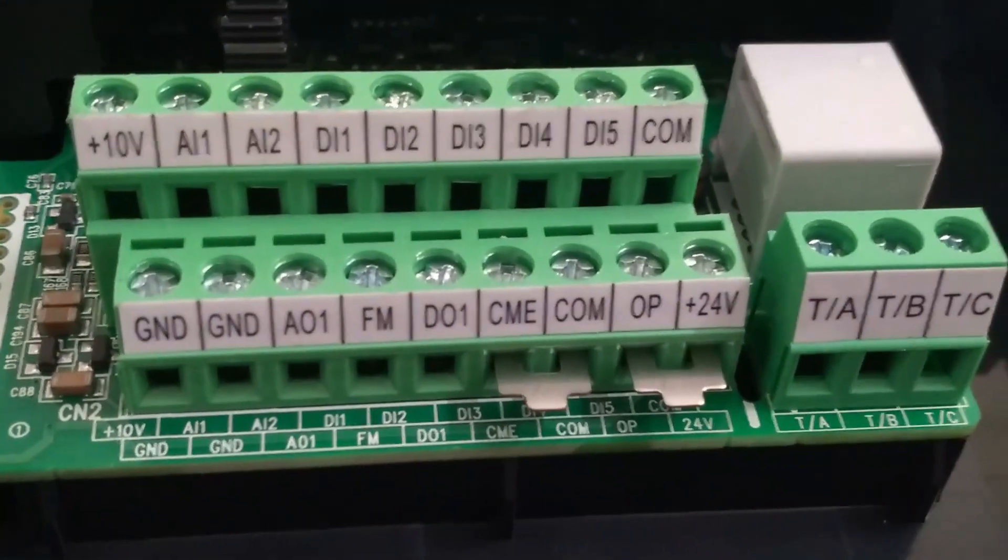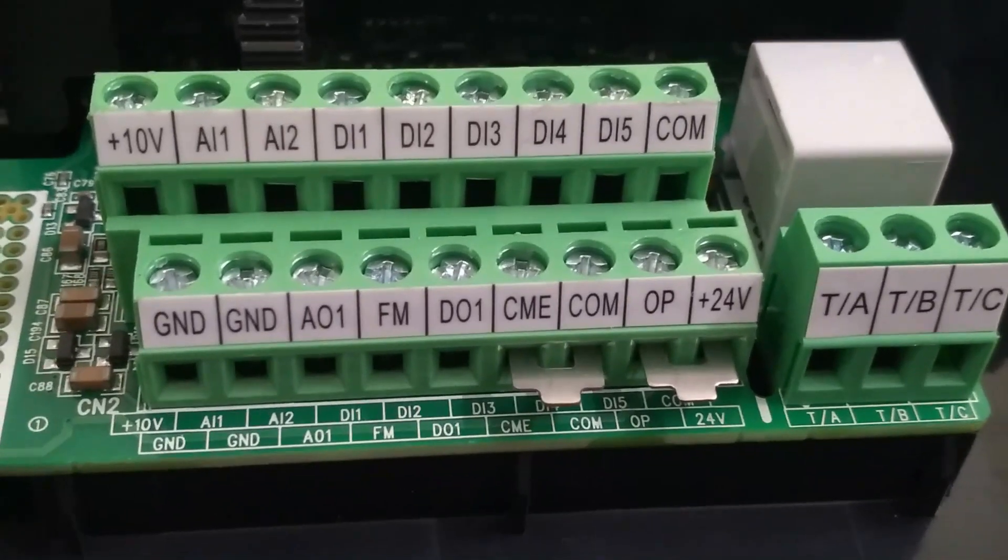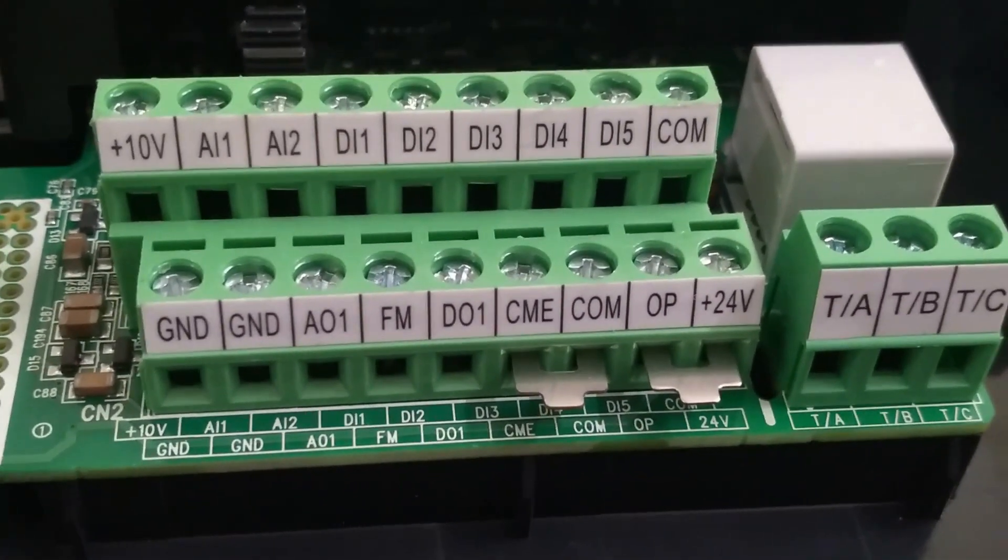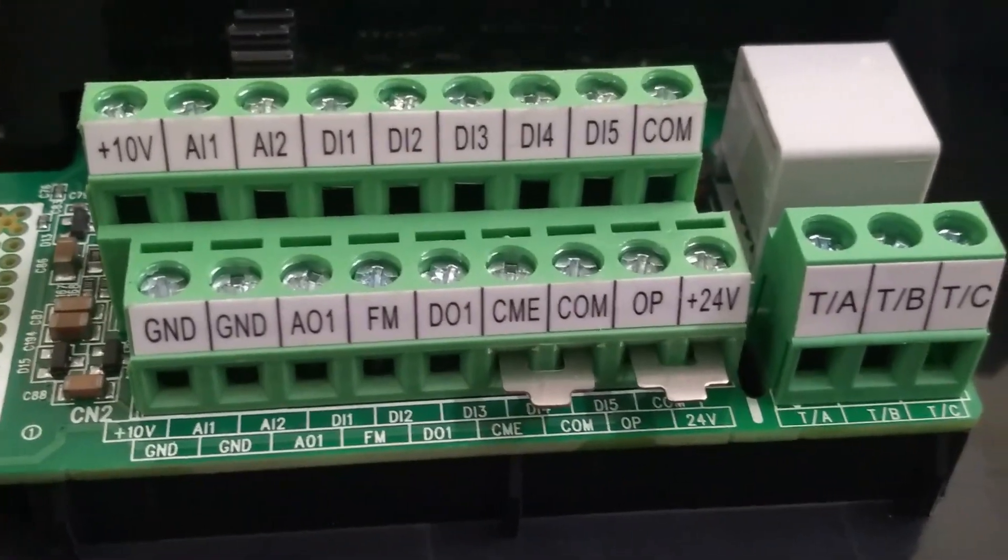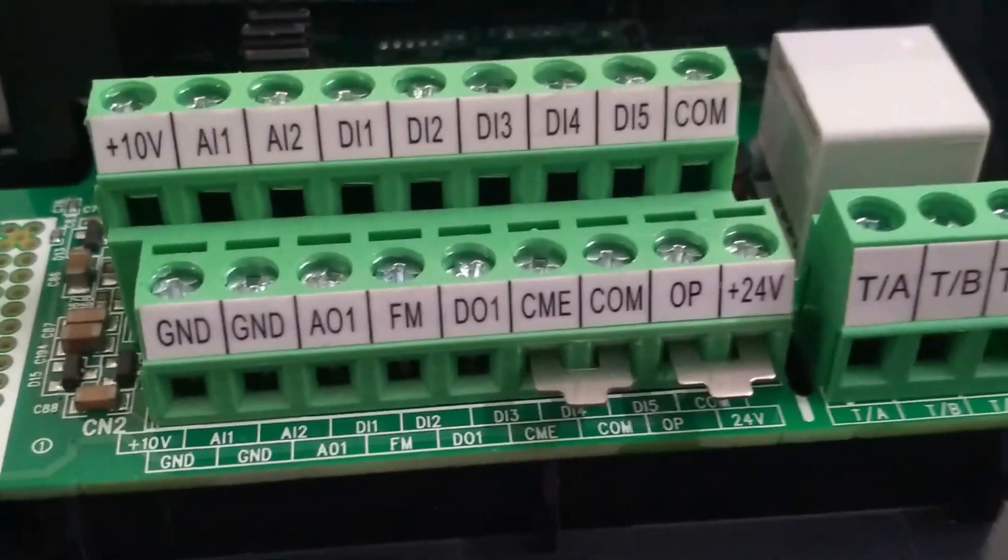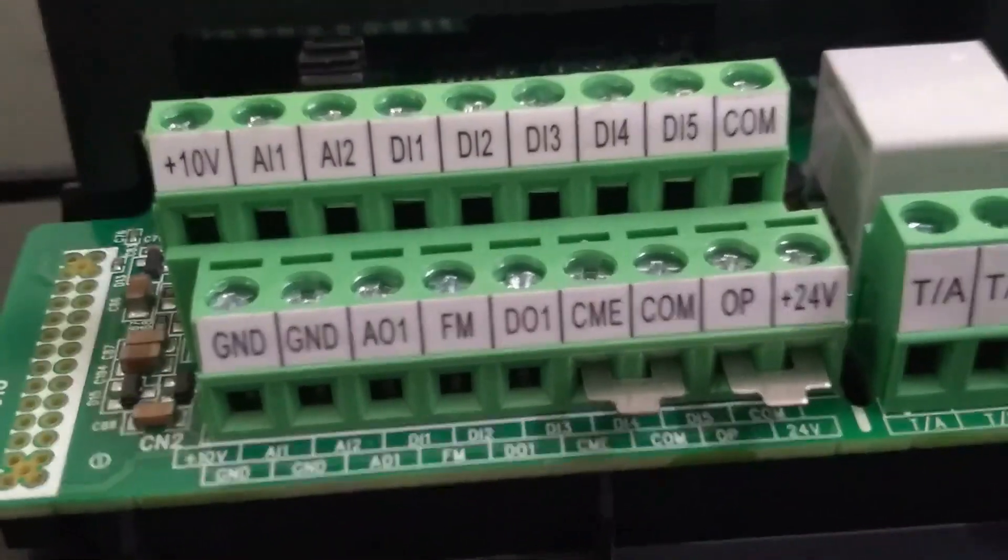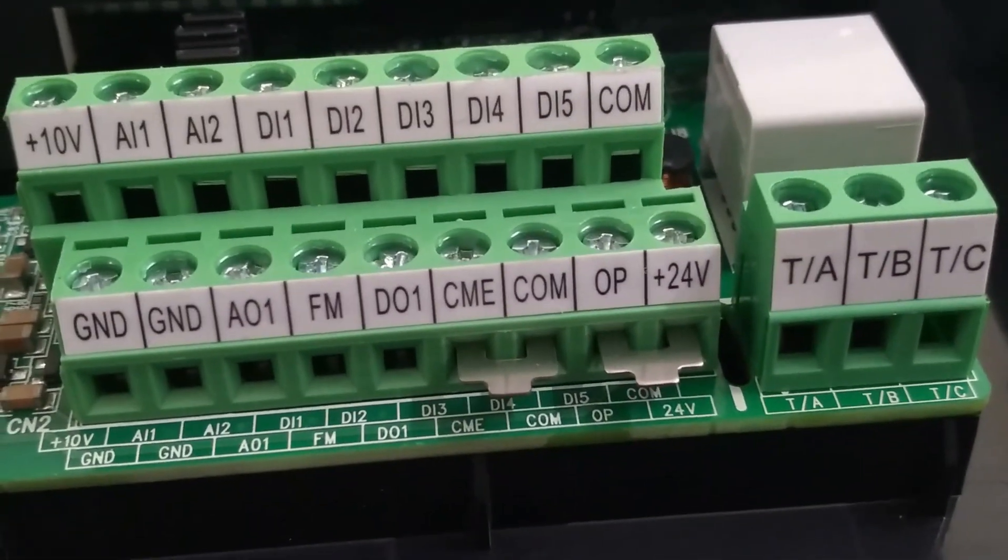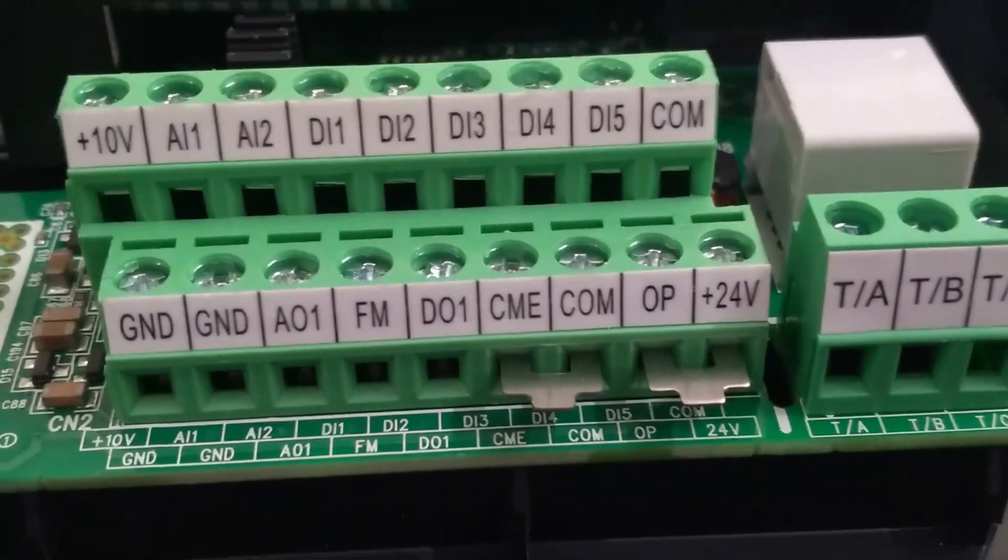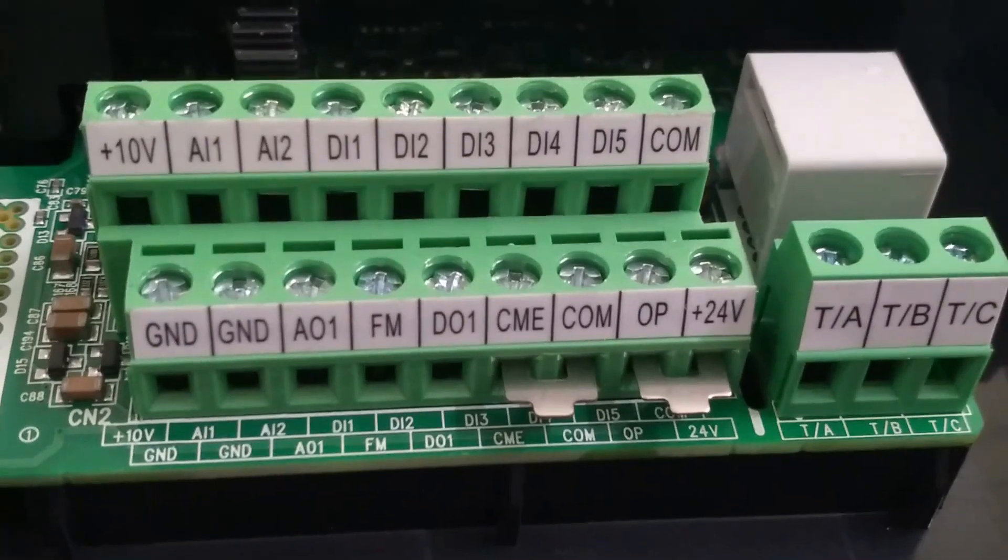COM is the common terminal of DC power supply. AI1 and AI2 are analog input signals. Analog input signal one wire will be connected to AI1 terminal and other signal wire will be connected to the GND terminal. GND is a ground terminal. Similarly, AO1 is an analog output terminal.